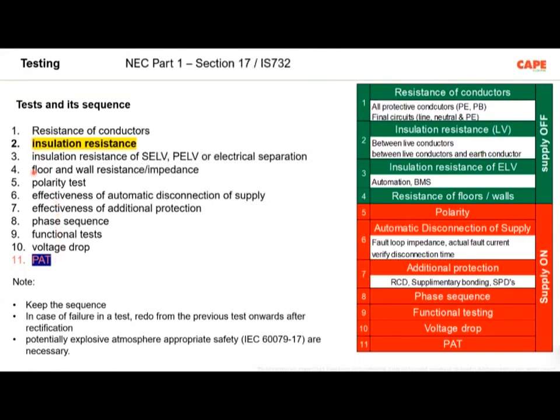The tests number 1 to 10 ensure that your electrical installation, the wiring and the protective devices, are operating in a very good condition. But tomorrow, if you plug in some device, portable devices are plugged into your good electrical installation, and if you have a portable device which is faulty, of course fire can happen.